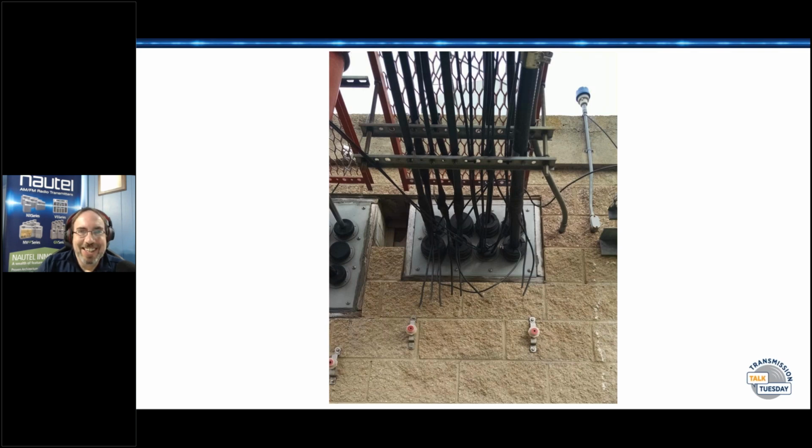Okay. That's why I picked you, because I knew that was your photo that was up there. This is John's picture, and what you're looking at is a really good reason to visit your transmitter site, to see if some copper thieves have made away with a good chunk of your ground plane. And they did. And it was replaced by the new owner of the site. Not as nice as the first one, but at least there's something there.